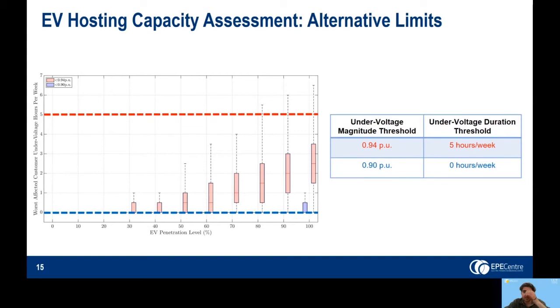These thresholds can be interpreted as follows. For the worst case customer, the voltage will not be less than 0.94 per unit for more than 5 hours during a week and will not be less than 0.9 per unit for any hours during the week. These thresholds are also shown on the plot now to the left.